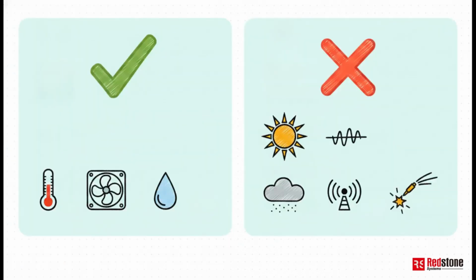So the real trick is balancing these strict operating bounds against hazardous extremes. In your comfort zone, the equipment room absolutely must maintain a temperature between 0 and 40 degrees Celsius, with humidity floating between 0 and 90%. Keeping things dry and well-ventilated is mandatory. But then you have the absolute do-nots. You have got to avoid direct sunlight, heavy vibration, dust, and any potential contact with water or oil. Furthermore, keep this gear far away from radio and cell phone antennas, electric welding machines, or high-frequency machines. Why? Because their electromagnetic interference will literally shred your signal quality.